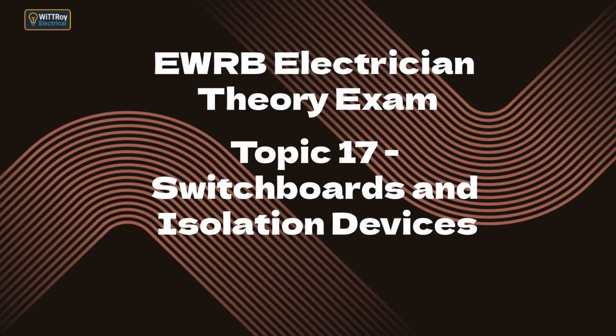Switchgear refers to the equipment used to control, switch, protect, or isolate electrical energy. This includes circuit breakers, fuses, isolators, load break switches, contactors, and any other devices used for switching or protection. These devices allow circuits to be turned on or off safely and to disconnect faults quickly enough to prevent damage or danger. So, the switchboard is the panel, the main switchboard is the first and most important one in the installation, and the switchgear is the equipment inside that does the actual switching and protection.